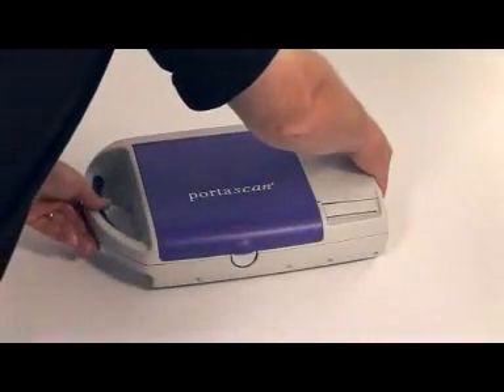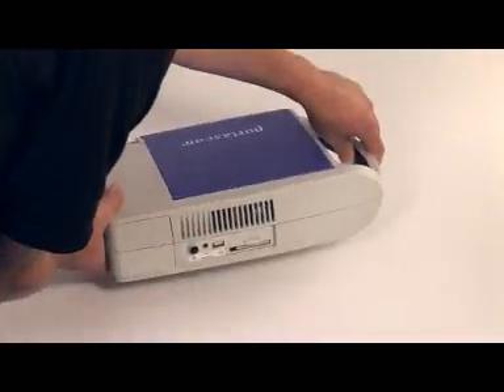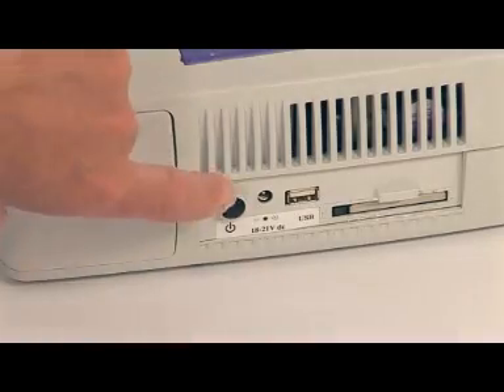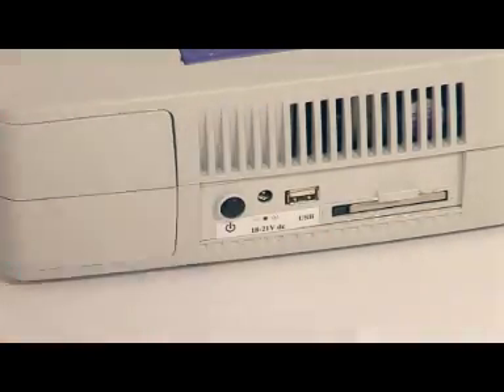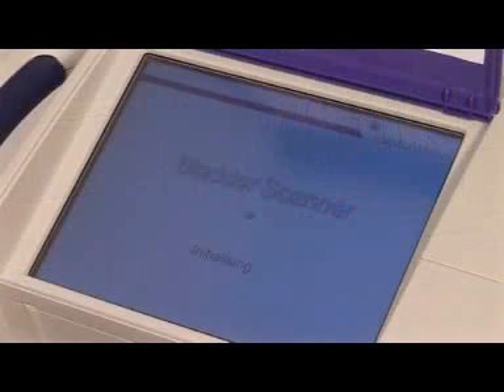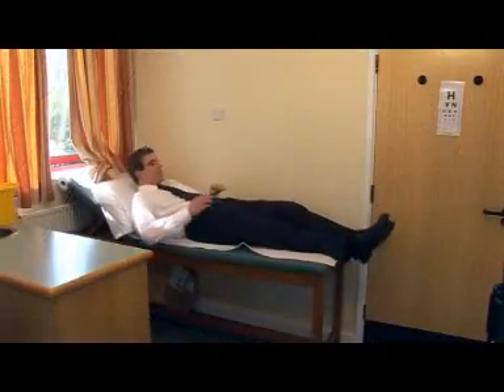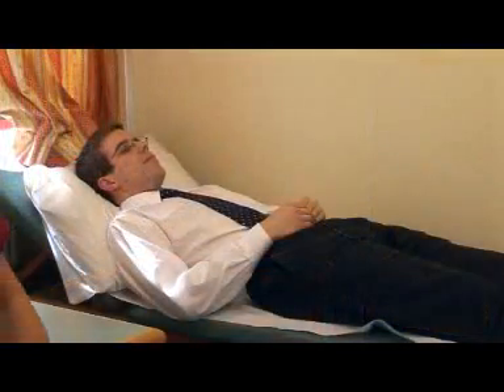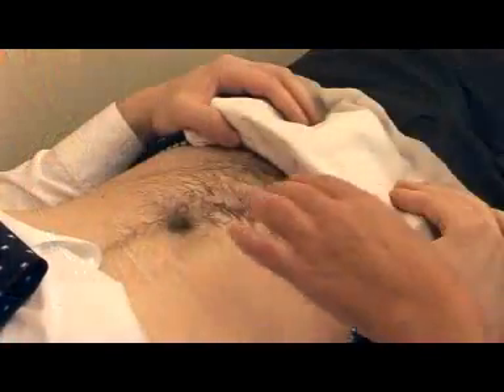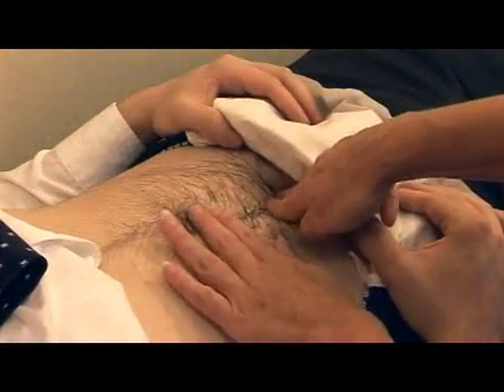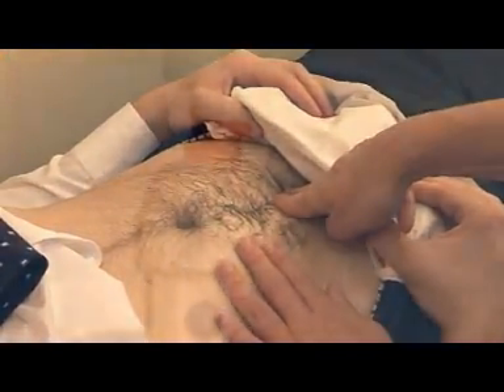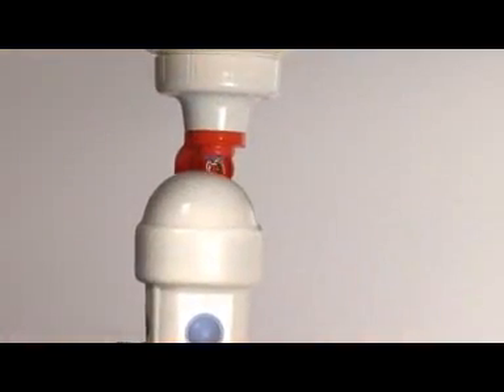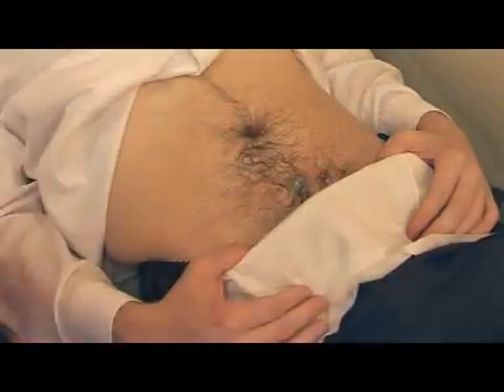Press the button on the back of the unit to start up the scanner. The scanner goes through some internal checks before it is ready, and it'll take approximately 90 seconds to complete these. Turn it on as you're preparing the patient. Get them to lie flat and relax, and start with the probe a couple of finger breadths above the pubic symphysis. Apply a squirt of ultrasound gel to the head of the probe or directly onto the patient's abdomen.